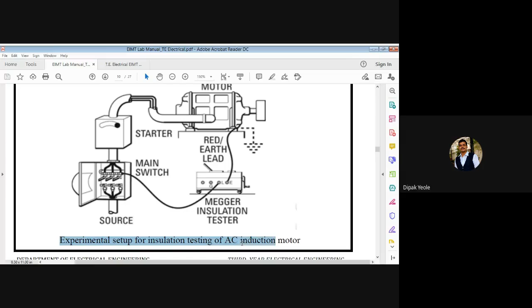Same way, we use the power cable, as they mentioned two equipments we are interested in. Here the power cable is available, a section taken and not connected to supply. There are 3 core conductor cables available. We use the insulation resistance tester with its 3 terminals: guard, line or live, and earth. The E terminal is connected to the body of this power cable.